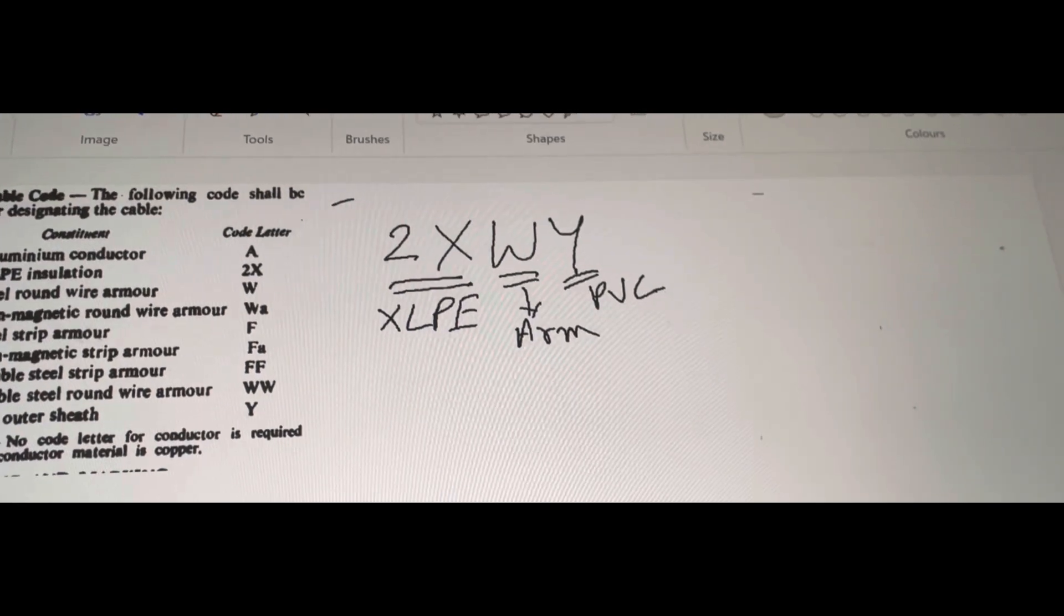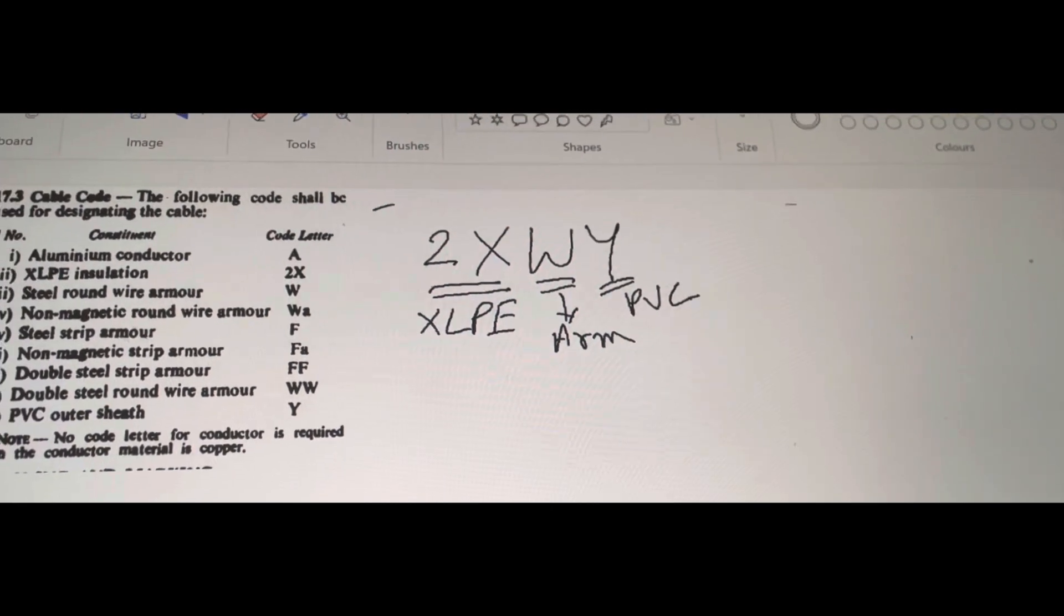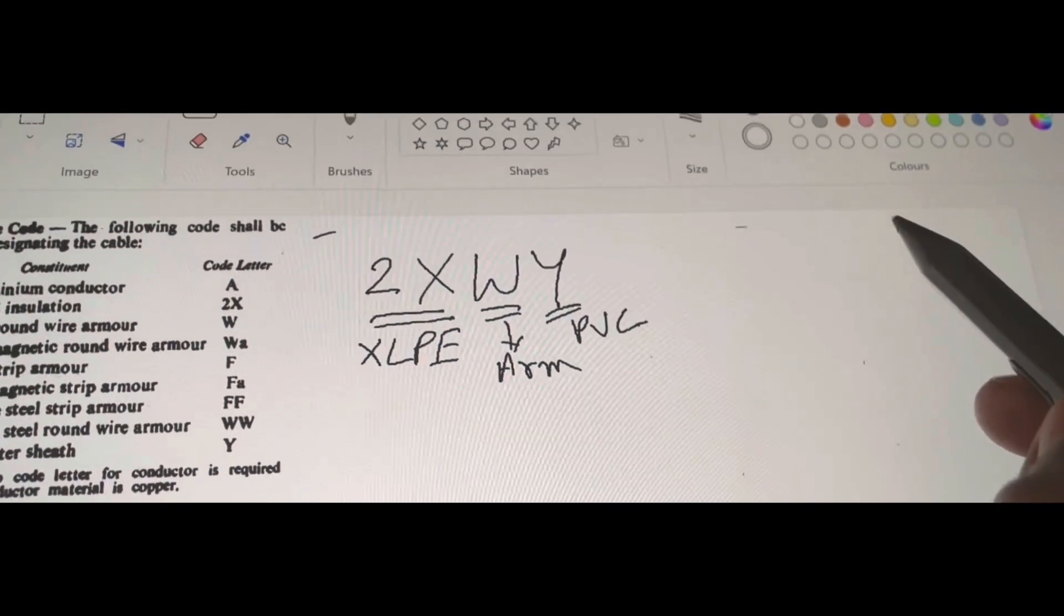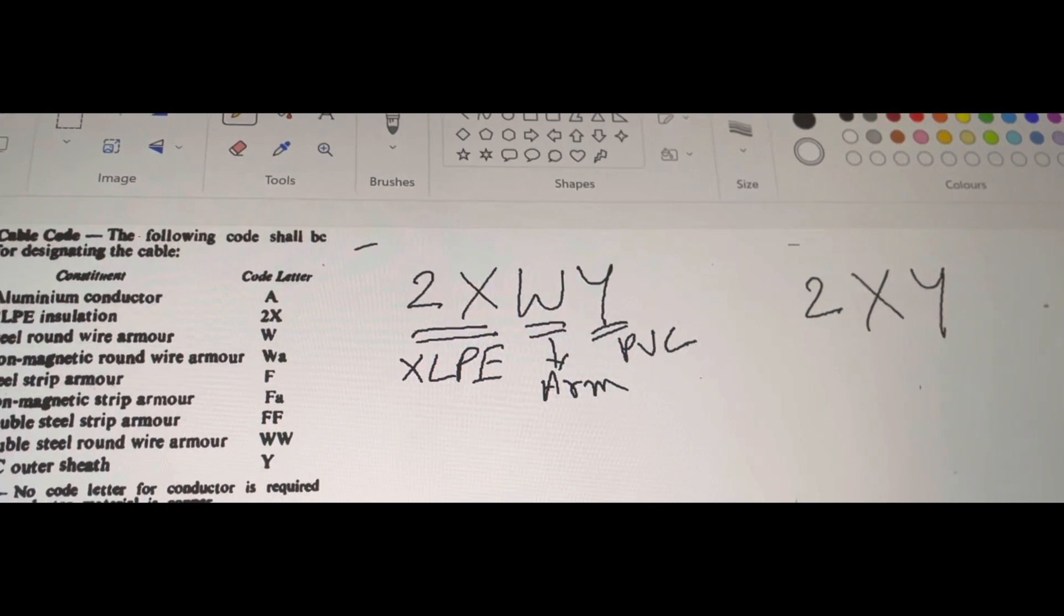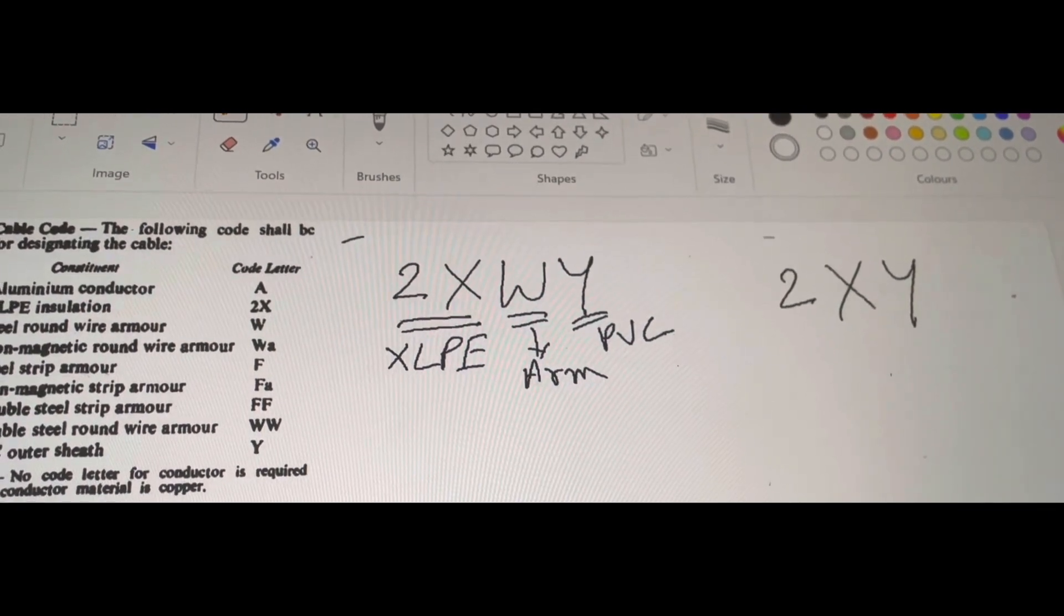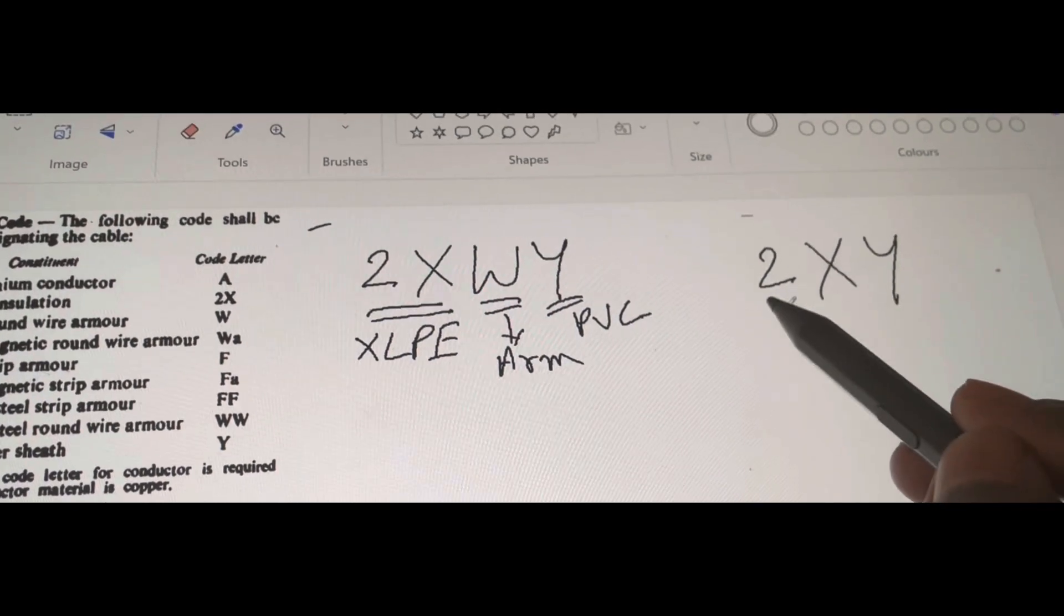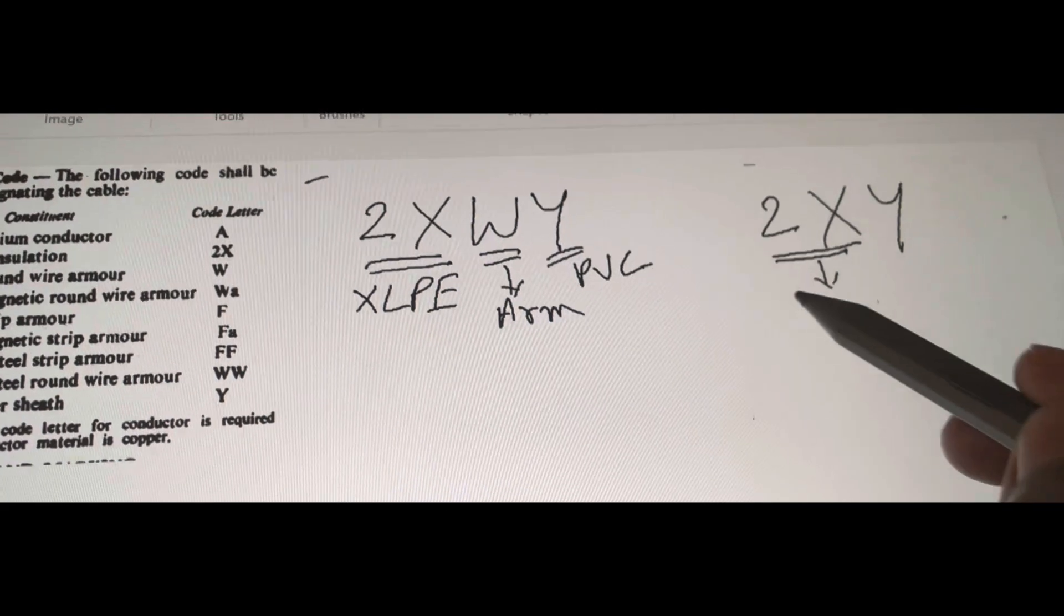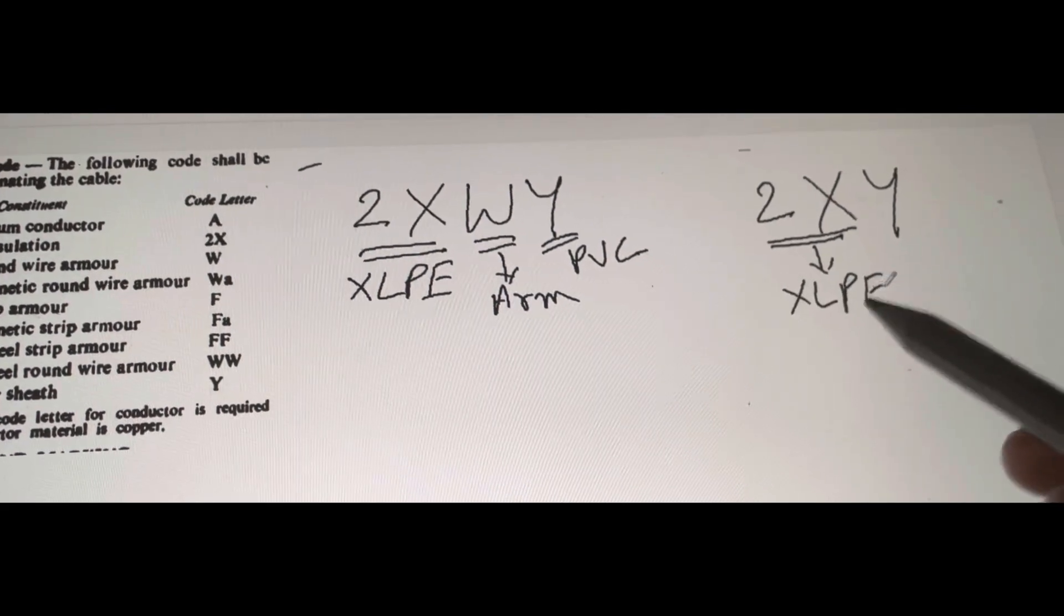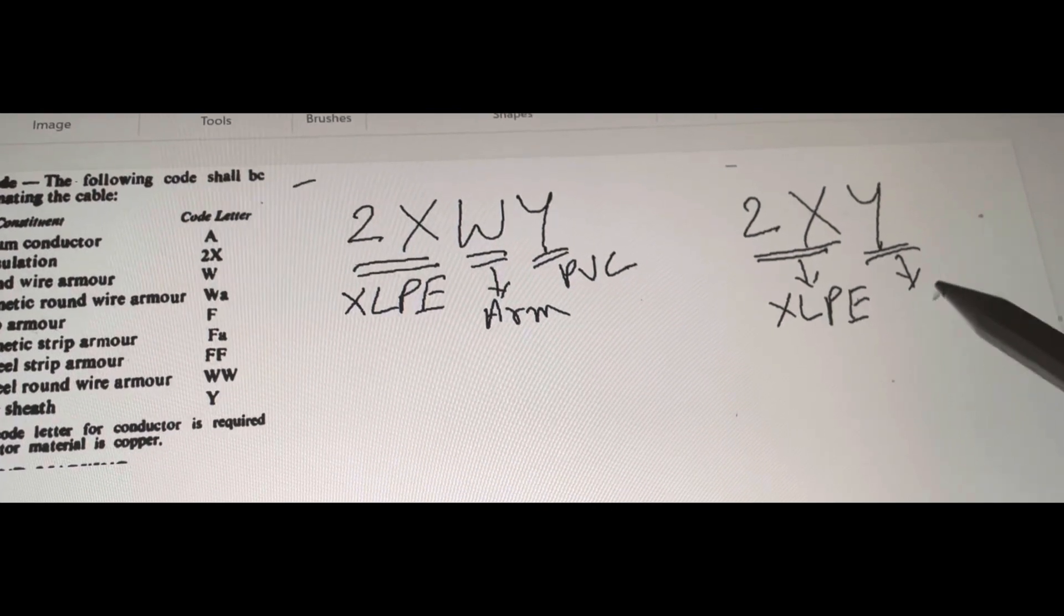In the same way, let us take another cable and assume that there is a code called 2xy. The code printed on that particular cable is 2xy. The meaning is 2x indicates that the insulation material is cross-linked polyethylene XLPE and y denotes the outer sheath is PVC.